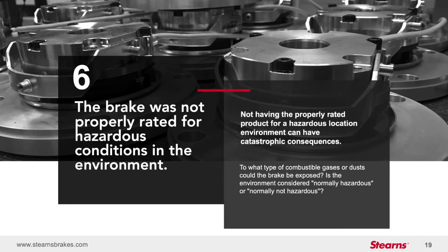Mistake number 6. The brake was not properly rated for the hazardous conditions in the environment. Hazardous locations are areas where flammable gases and vapors or combustible dusts exist in sufficient quantities to produce an explosion or fire. In hazardous locations, specially designed equipment and special installation techniques must be used to protect against the hazardous potential of these substances. It is possible to have a properly rated brake for a hazardous location but improper installation. Not following UL guidelines, these mistakes can nullify the brake's hazardous location rating.